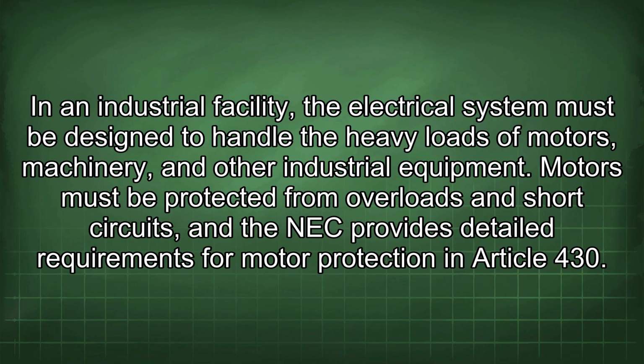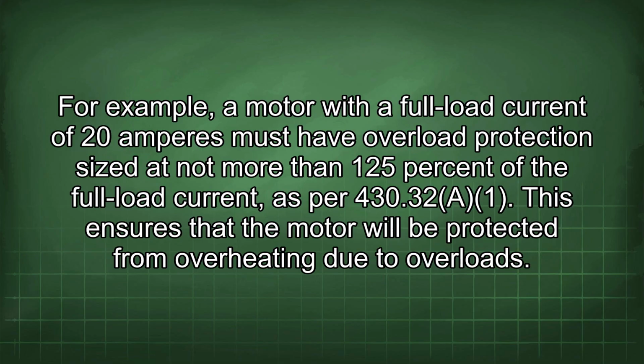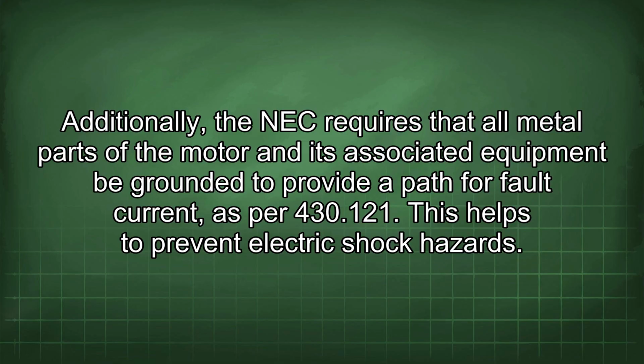In an industrial facility, the electrical system must be designed to handle the heavy loads of motors, machinery, and other industrial equipment. Motors must be protected from overloads and short circuits, and the NEC provides detailed requirements for motor protection in Article 430. For example, a motor with a full load current of 20 amperes must have overload protection sized at not more than 125% of the full load current, as per 430.32(A). This ensures that the motor will be protected from overheating due to overloads. Additionally, the NEC requires that all metal parts of the motor and its associated equipment be grounded to provide a path for fault current, as per 430.121. This helps to prevent electric shock hazards.